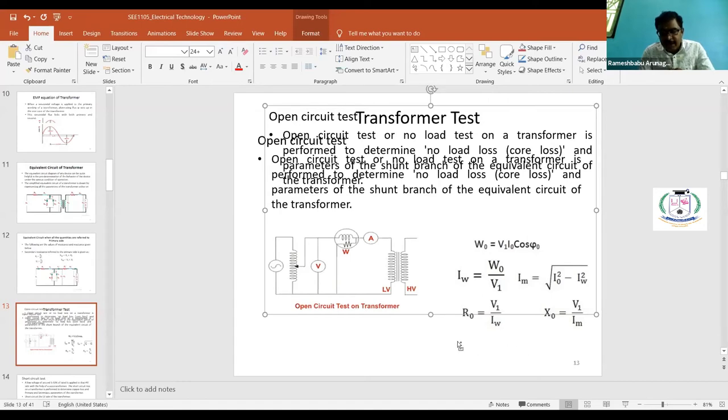IW is nothing but the core loss current. IM is the magnetizing current. R0 is the core loss component resistance, and X0 is the magnetizing reactance. These are the components you can find out. The wattmeter value is nothing but the core loss of the machine. From this test, I can calculate the core loss and the no load component values.